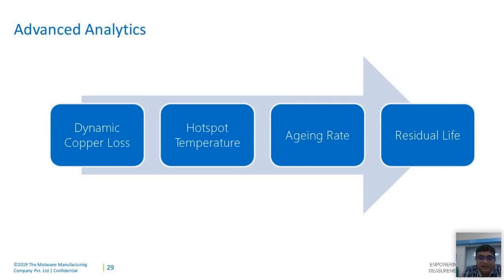So based on this sampling of data, based on certain categories, we can also predict when this value is going to hit the limit if it is operated at a certain percentage with certain ambient conditions. This can send a pre-alert to the users to see whether the cooling system is turned on prior to it actually hitting the temperature, or to take some kind of corrective actions, possibly adjusting the loading on that particular transformer based on the scenario or control they have over the loading part.